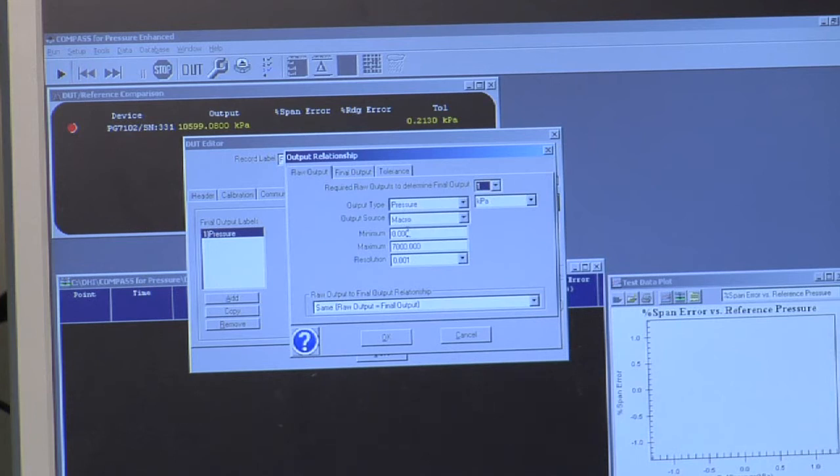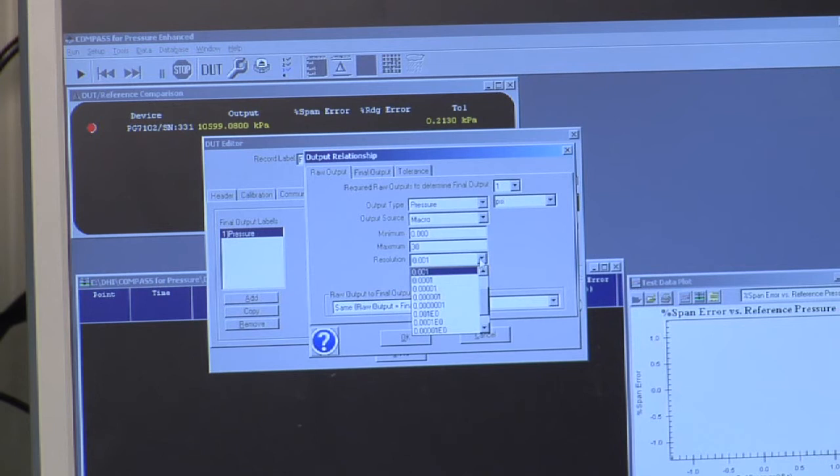So this range, of course, the software doesn't know the range because I just chose an example. If I double click this field, I can define the actual range of the instrument. I can define the resolution associated with the device. This is very important because if you have the wrong resolution, your data is not going to come out the way you expect it to.